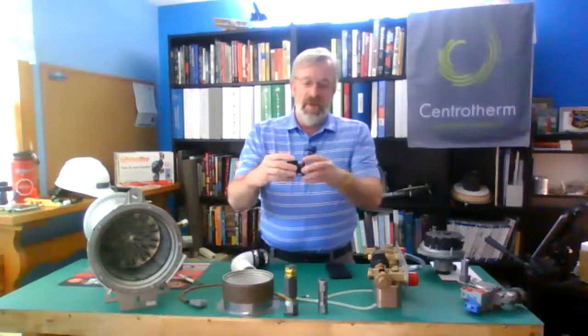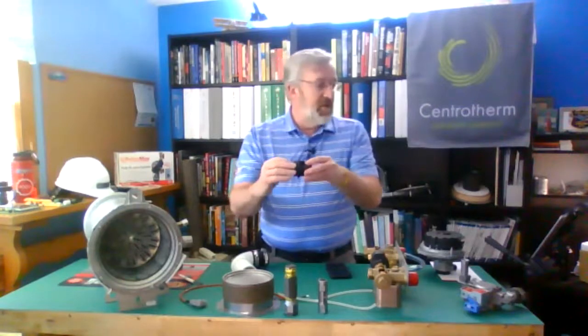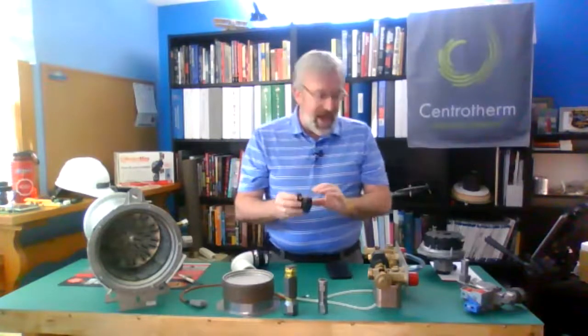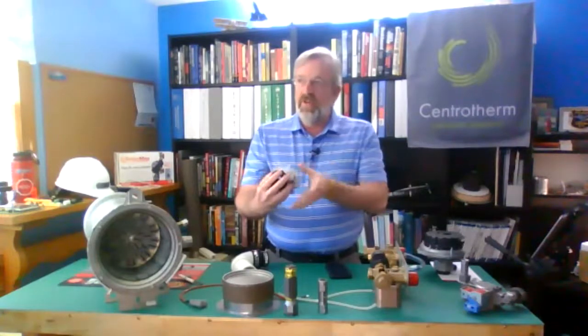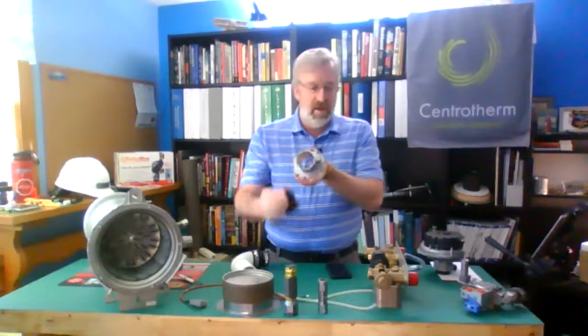Depending on where I am on the fan speed, there's a flapper in here that opens and closes. At times, I'm going to draw just across the bottom orifice. At times, I'm going to draw across the bottom and the top orifice, really depending on how fast we're going. That's going to create the air sucking, because it creates negative pressure, the gas in. Since this inserts right in here, I'm creating that suction within this venturi.